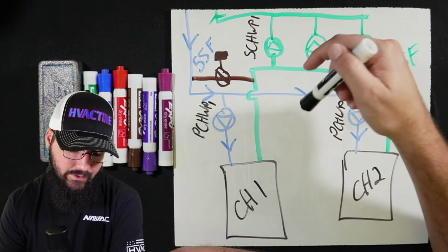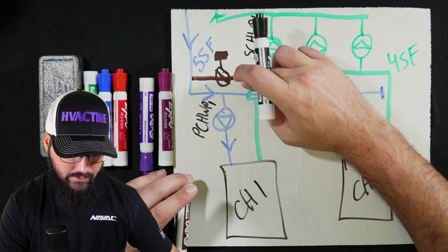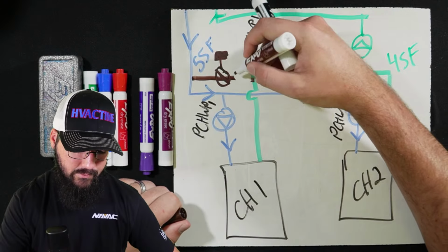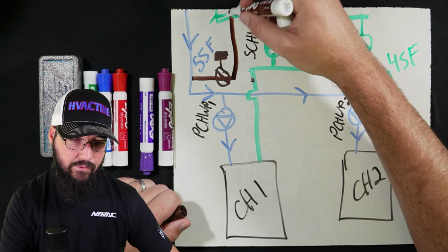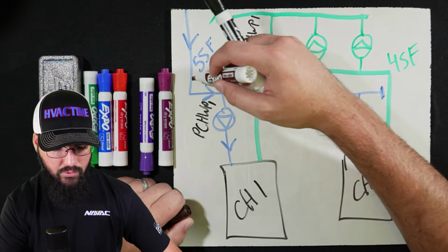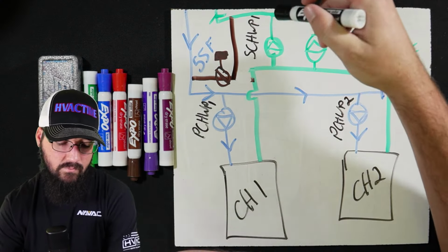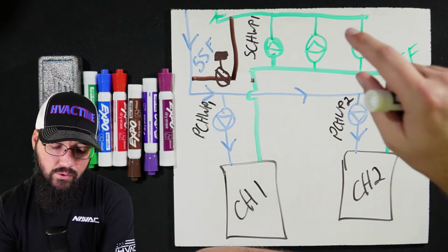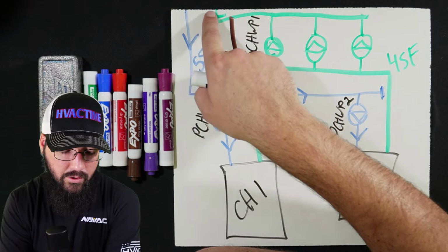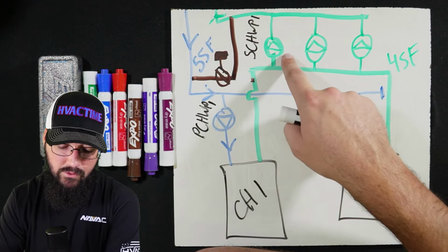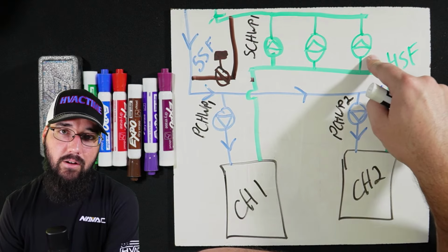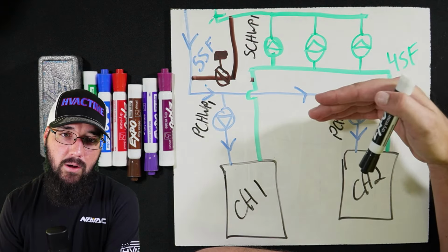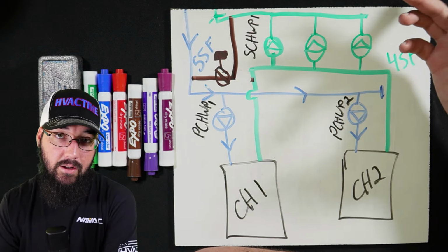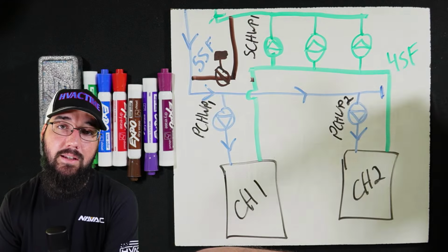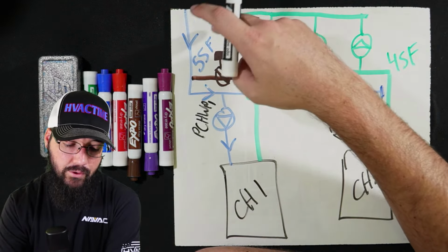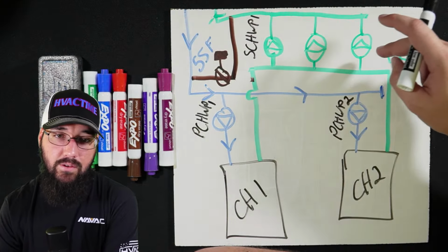And again, this bypass, I'm just going to have to fix it. It's going to bother me too much. This bypass doesn't go from here. It actually goes from up here. So we're going to bypass from this side of the header to the incoming side of the header. That way we can balance our DP. So we're monitoring our DP here. That DP will affect how many secondaries we need on. So as our pressure begins to drop too low, we need to either speed these secondaries up if they're on a drive, or turn more on to get that DP back up. And we're going to be controlling solely based off of that for these secondaries.